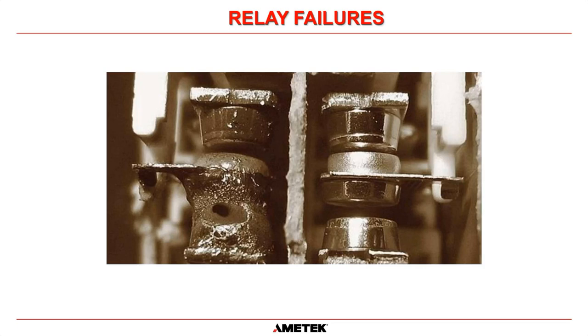And the other thing that happens with relays is they can weld closed. You can see this one here. This is what it should look like. Nice, shiny and clean. But these contacts here have welded. The arc melted some of the copper, and the plasma in the arc was so hot that it allowed other parts of the metal to evaporate and basically cause these contacts to weld together. So if you replace relays on a regular basis, this should not happen. Okay.